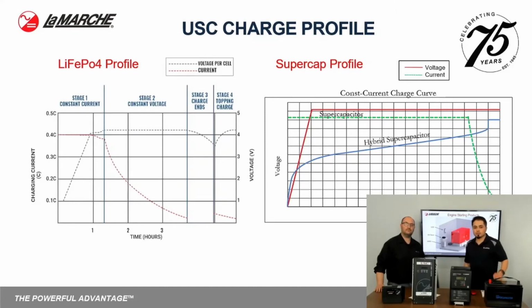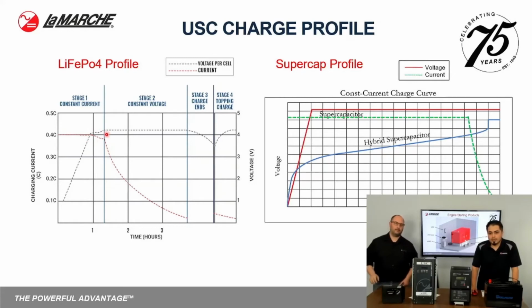Going into the charger profiles that I mentioned just a moment ago, the LiFePO4 profile, which is lithium iron phosphate. As you can see here, you still have your same stage 1, which is your bulk stage. Once you reach that higher voltage level, you do still remain in that voltage level, your float level I guess you would indicate it as, where your current starts to taper off much quicker and much faster. I have seen other instances where this is actually done within maybe 15 minutes instead of 3 hours, but again, this is definitely dependent on the size of your charger and your battery as well.